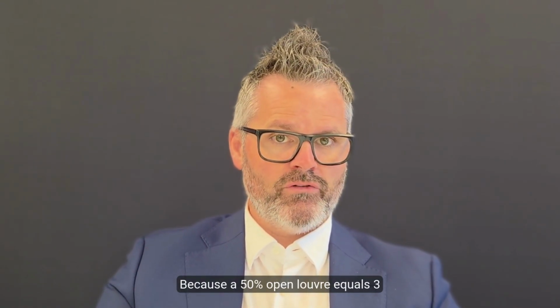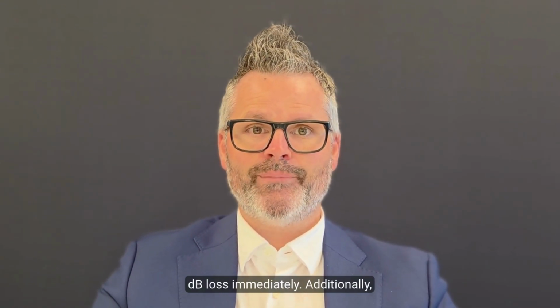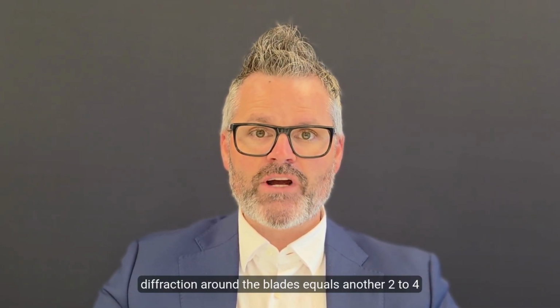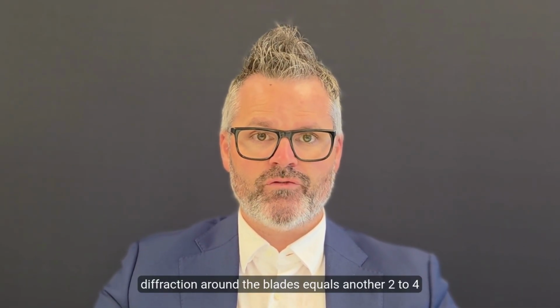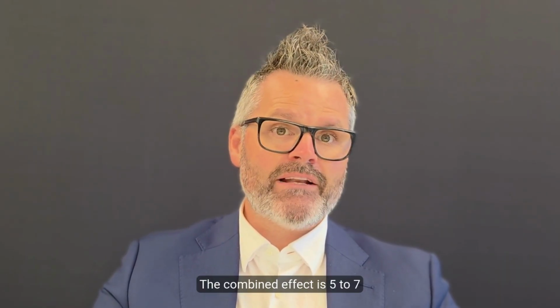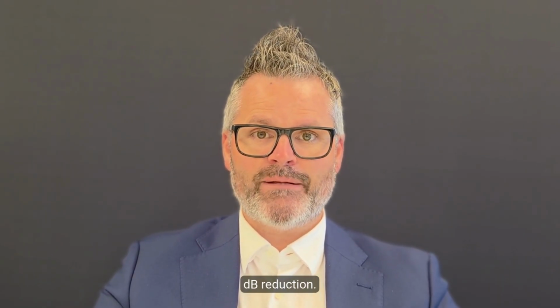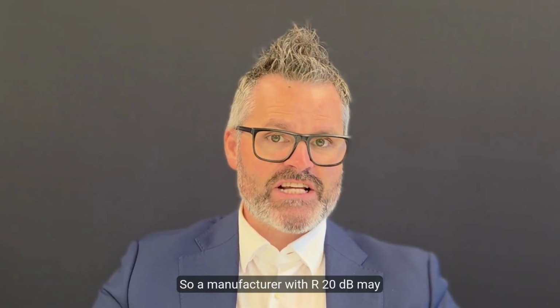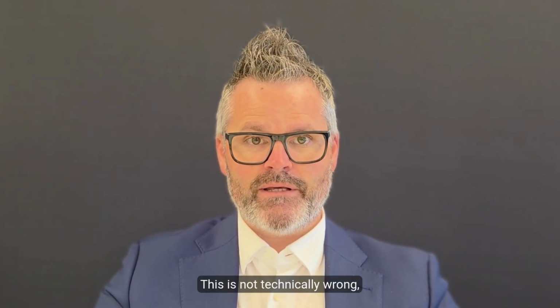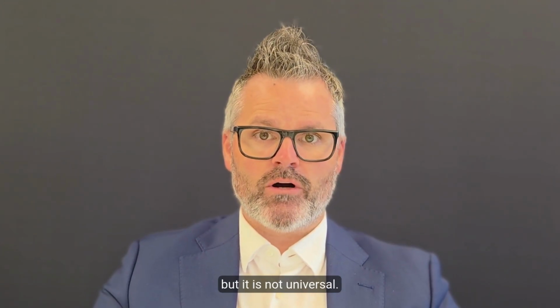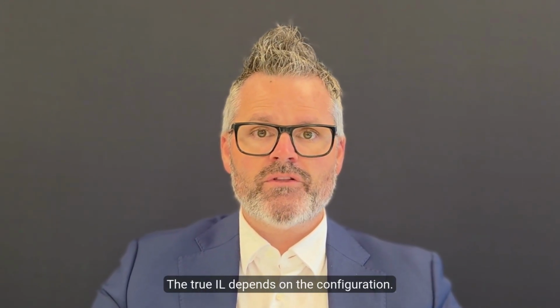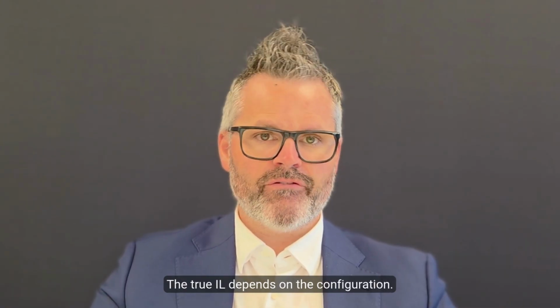Why 6 dB? Because a 50% open louver equals 3 dB loss immediately. Additionally, diffraction around the blades equals another 2 to 4 dB. The combined effect is 5 to 7 dB reduction. So a manufacturer with R 20 dB may list IL as 14 dB. This is not technically wrong, but it is not universal. The true IL depends on the configuration.